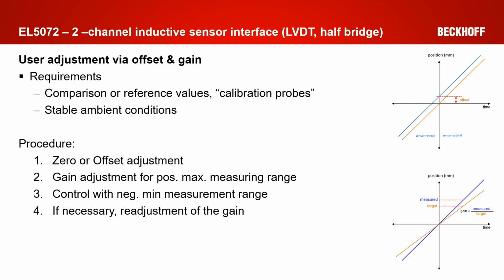These are fixed in temperature-stable resistance, and they reflect a certain position, for example, the zero or some calibration measurement ranges. Furthermore, of course, stable environment conditions, such as temperature, must also be observed. The procedure for such an adjustment can be as follows. In the first stage, you can carry out a zero offset adjustment. So, for example, you will move to the mechanical reference zero and look at the output value of the terminal. Then you can write this value inside the offset register.